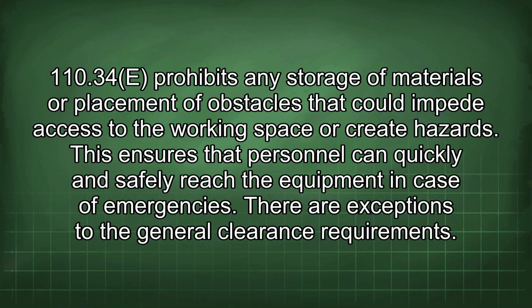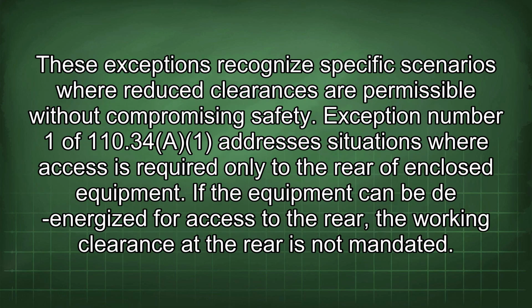110.34(E) prohibits any storage of materials or placement of obstacles that could impede access to the working space or create hazards. This ensures that personnel can quickly and safely reach the equipment in case of emergencies. There are exceptions to the general clearance requirements. These exceptions recognize specific scenarios where reduced clearances are permissible without compromising safety.